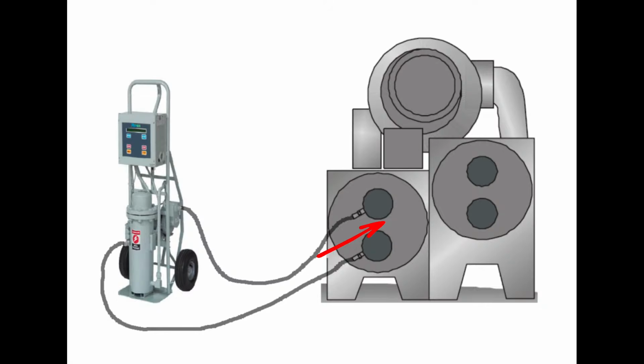And I do mean fully isolate on both inlet and outlet on both barrels, not just having an ISO to stop flow. I want to actually completely isolate this from the rest of the circuit. So this has a pressure transducer that can connect. You can set a pressure setting. So if I'm just doing a regular routine service, once I get to 1 psi, I'm happy. I can change my purge filter, I can change my oil filter, I can do all the regular service.